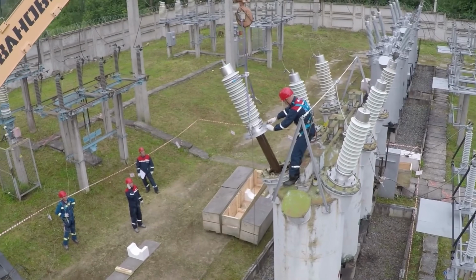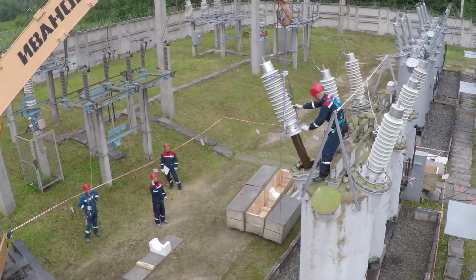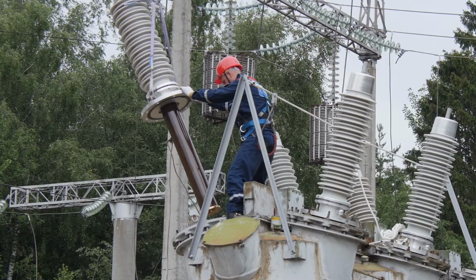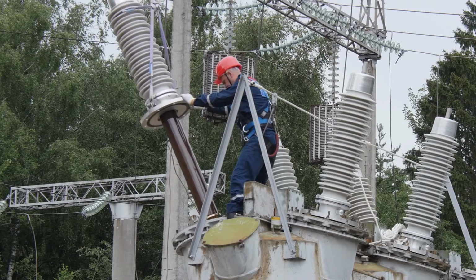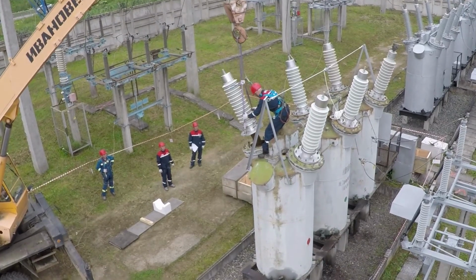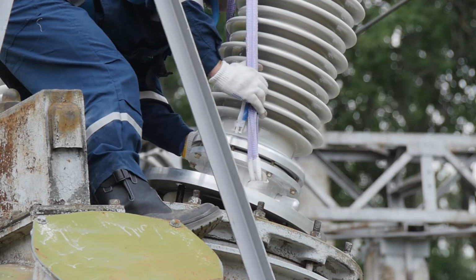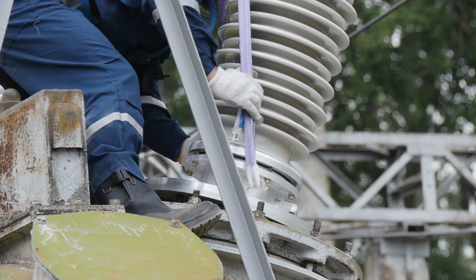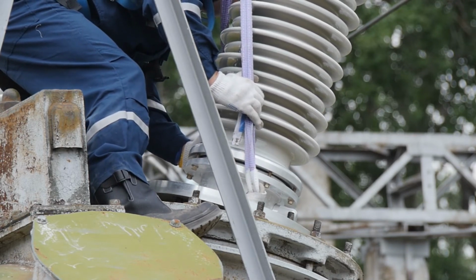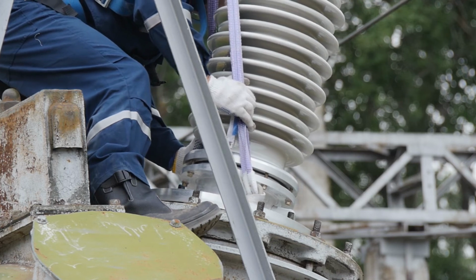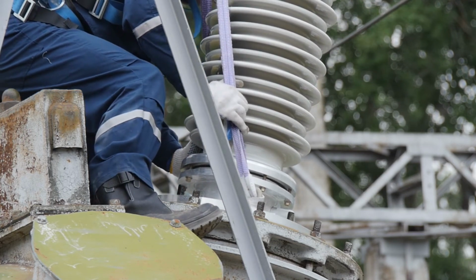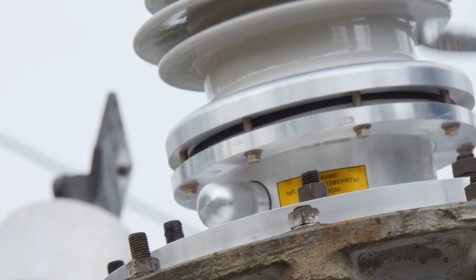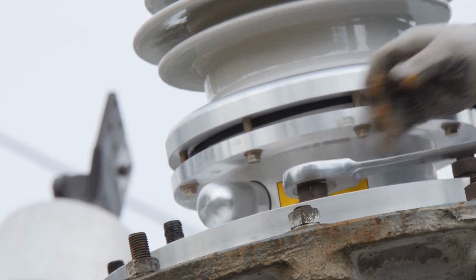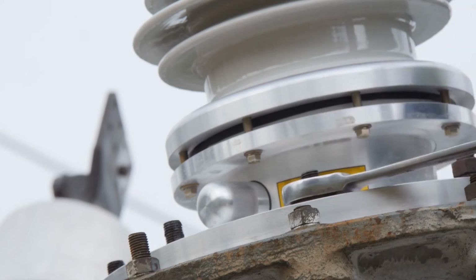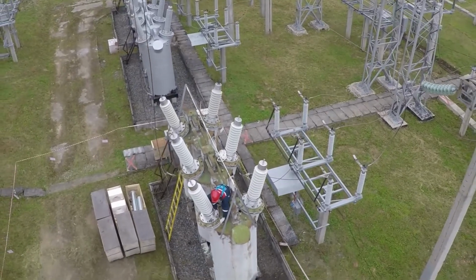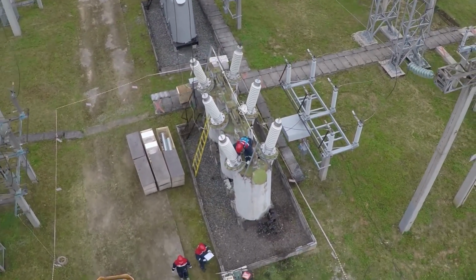Before installing the bushing onto a circuit breaker tank, check the position of the rubber gasket inside the mounting flange groove. Carefully bring the bushing to the circuit breaker and align it properly with an installation point on the circuit breaker. Mate the bushing flange holes and the circuit breaker tank pins and carefully install the bushing. Tighten the mounting flange bolts evenly around the circumference, avoiding over-tightening of separate fasteners.